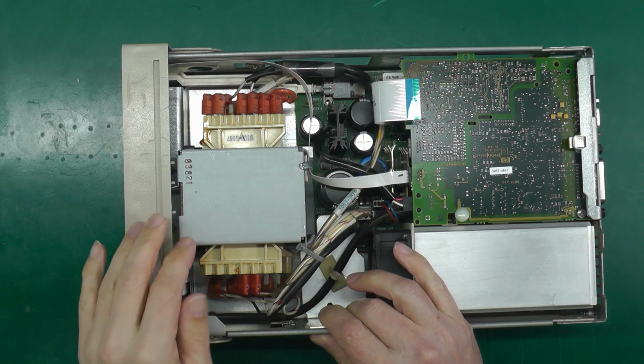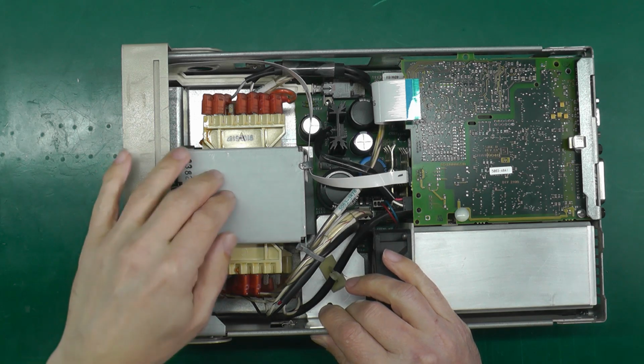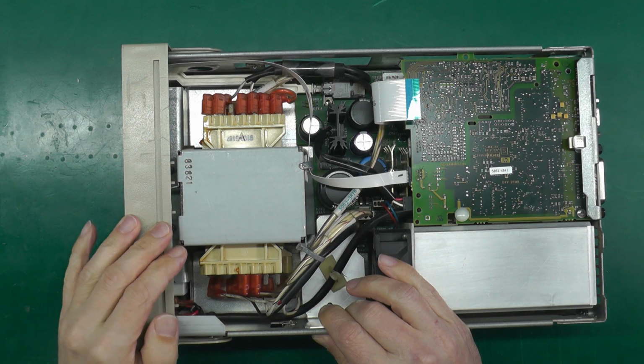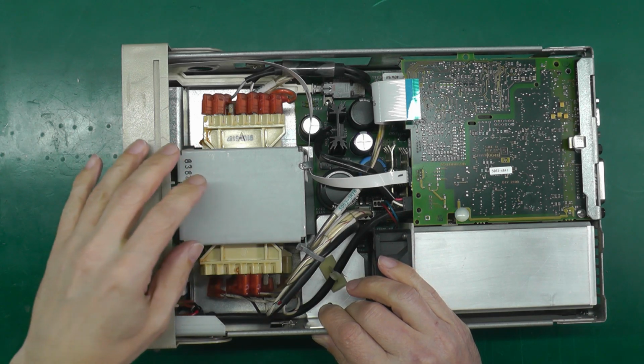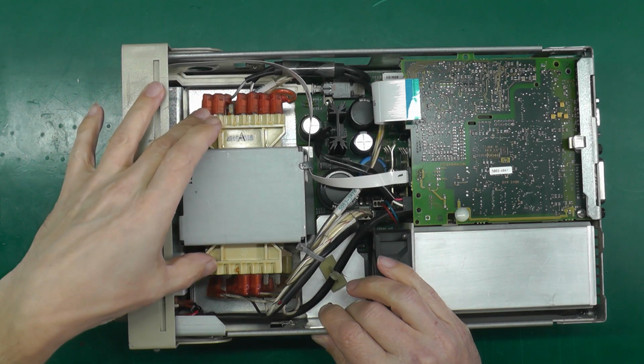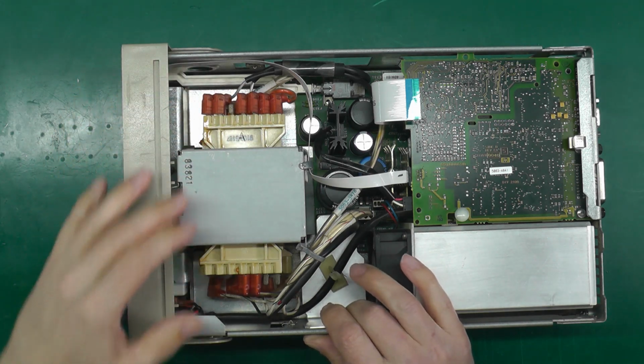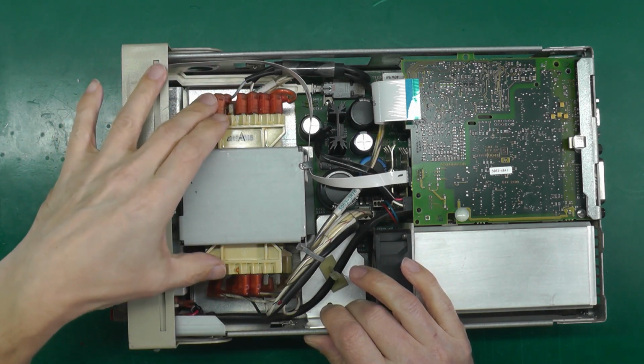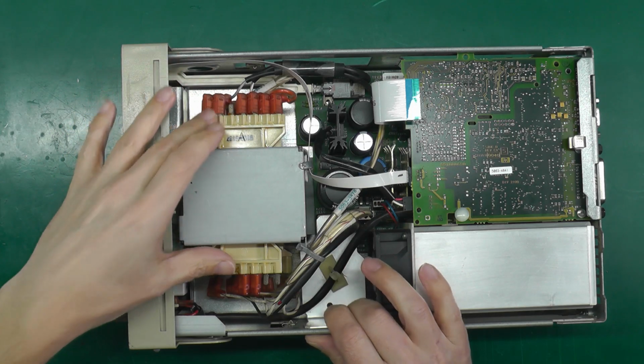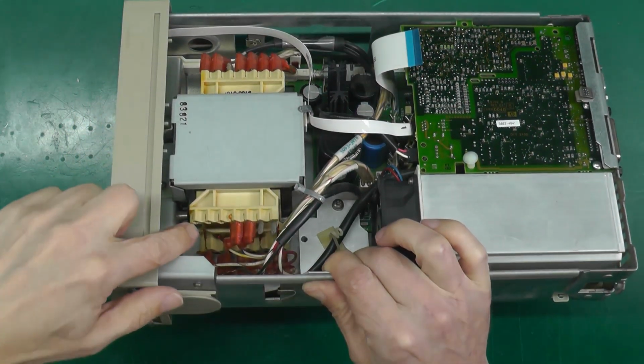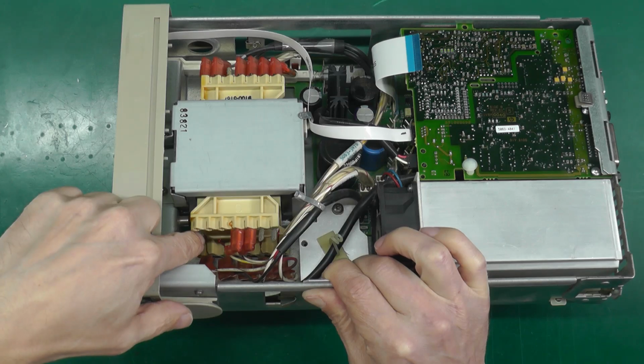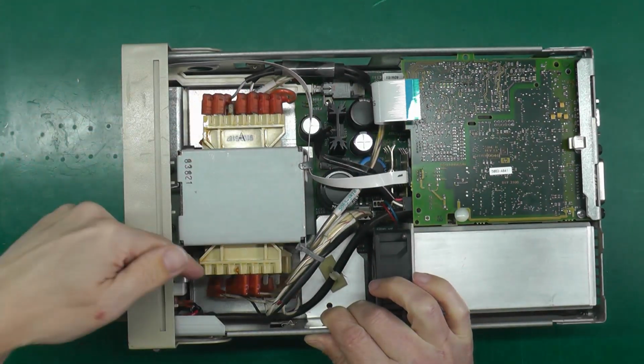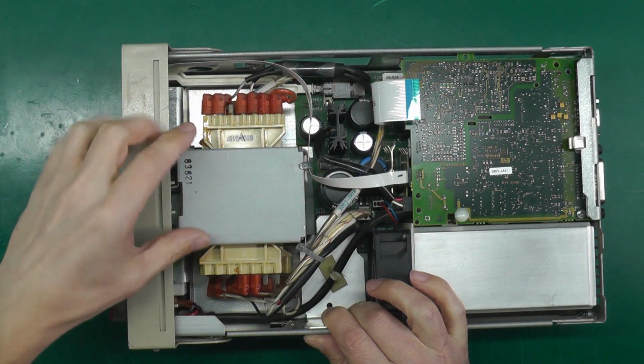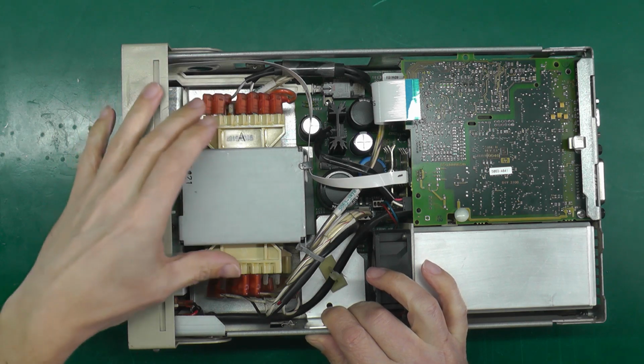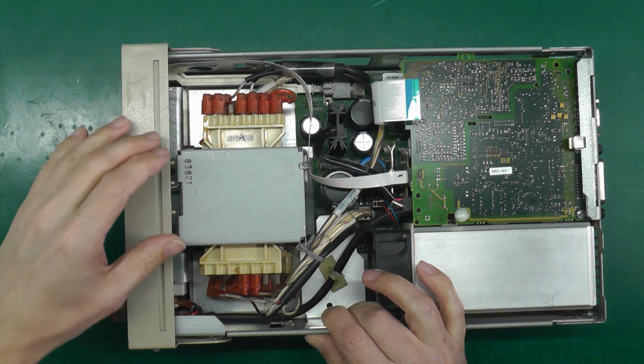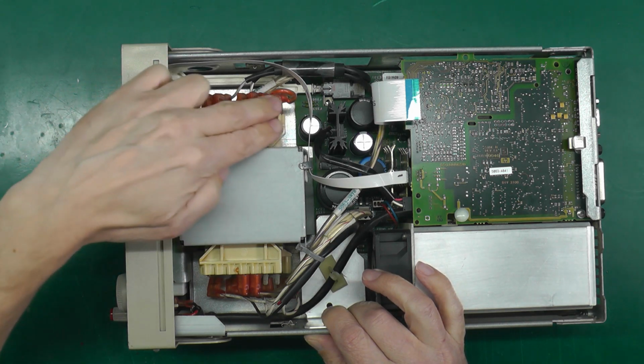Right, like I said, before we power it up, I need to set this unit to 230 volts. Big transformer here. There's actually 4 sets of connections on it. You can see the spade terminals there for the top 2 banks of connections, but if you look down in there, you can see at the bottom side of the transformer on both ends there's connections as well.